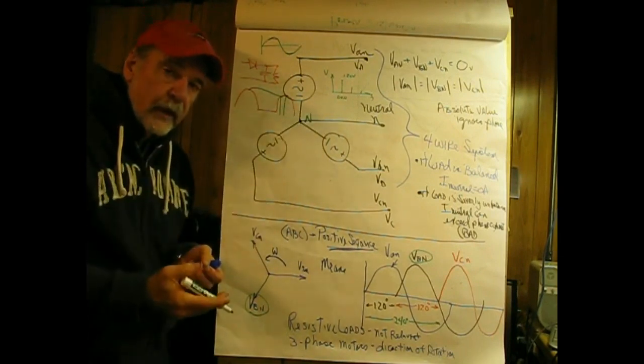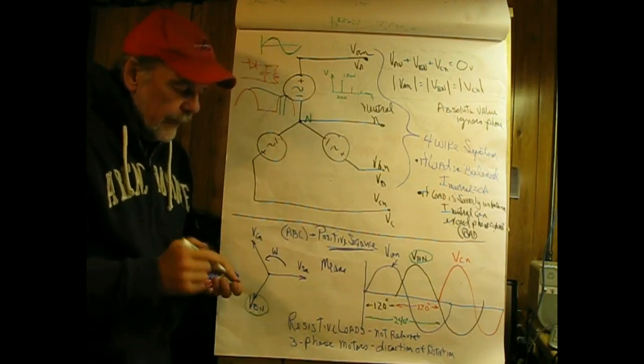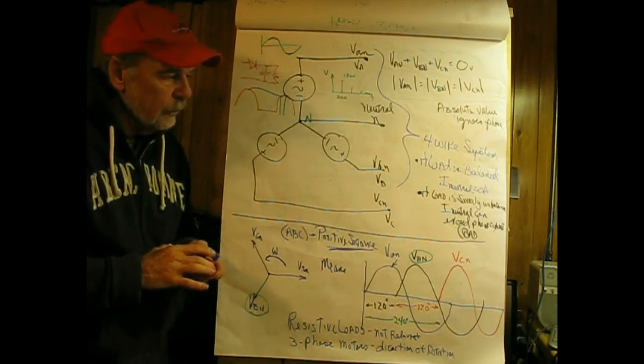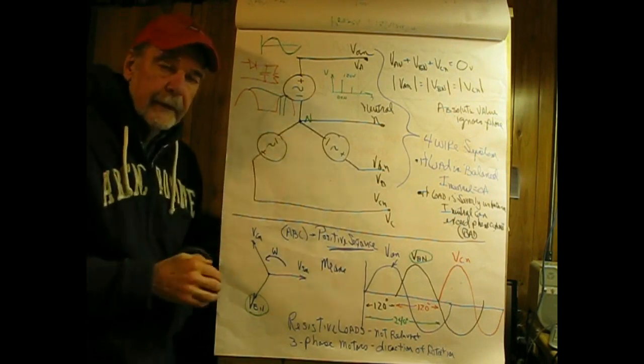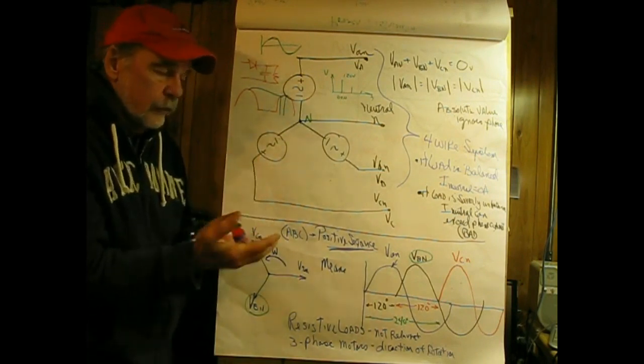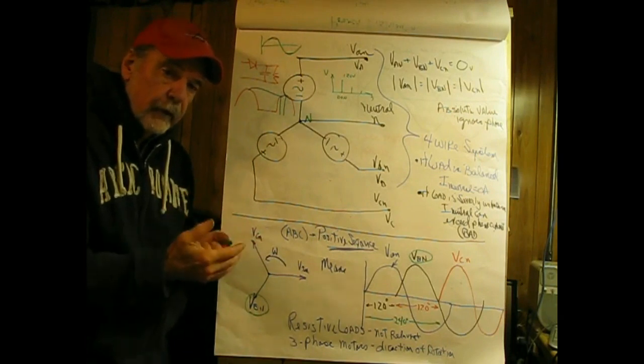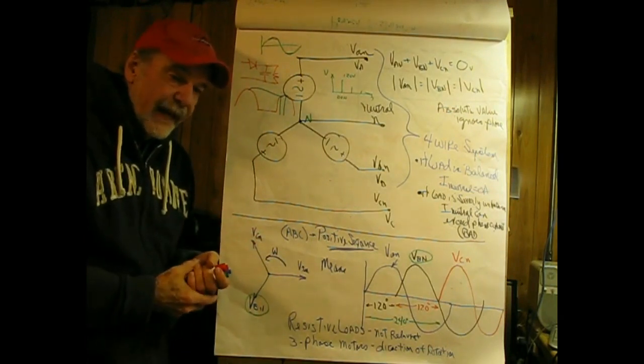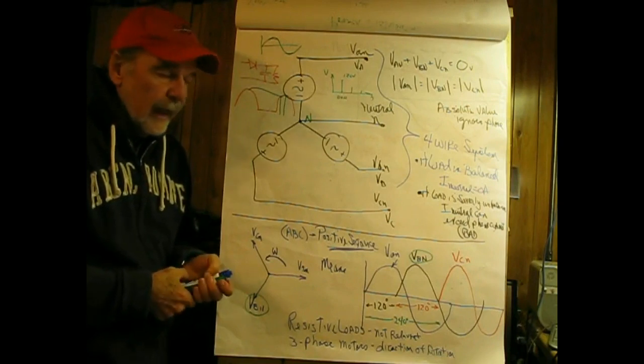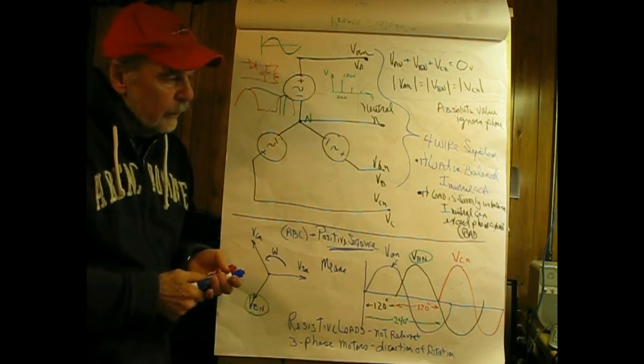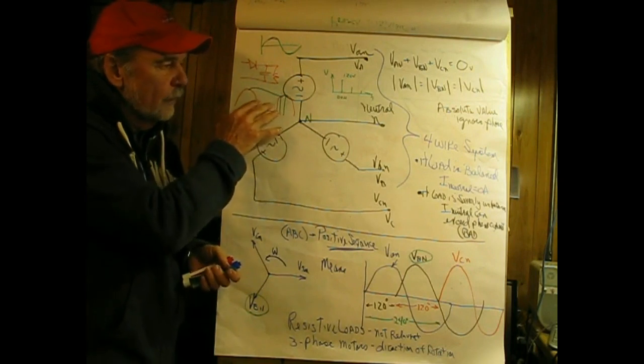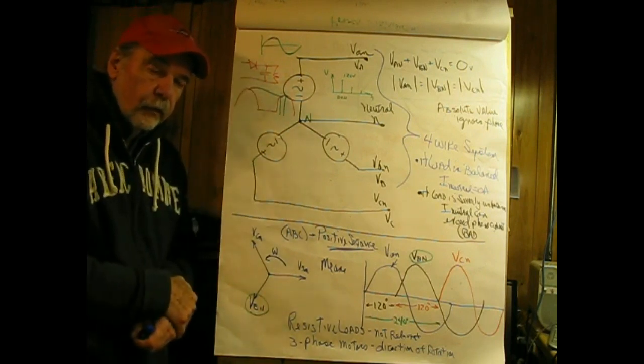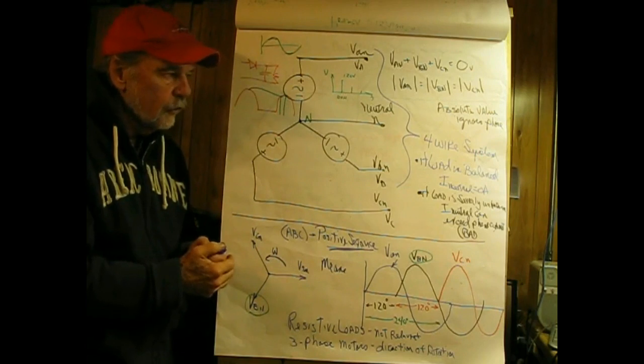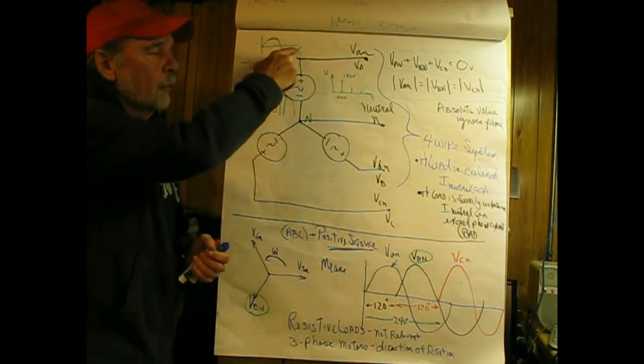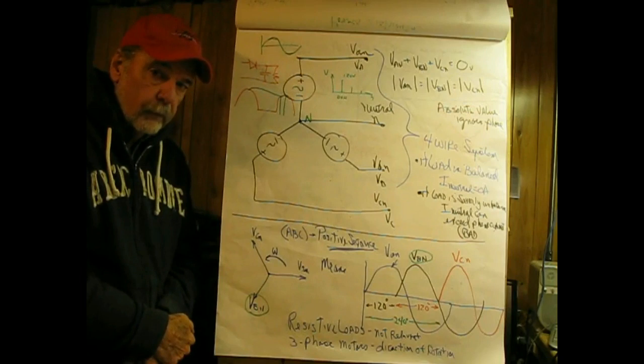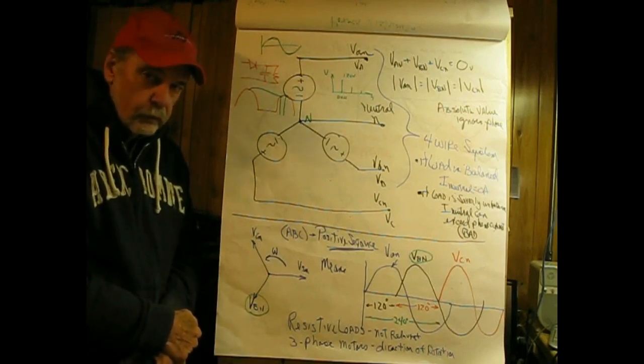They're producing currents which basically flow inside the plant, reducing the transformer's ability for the core to not saturate, causing I squared R losses and so forth. So modern power supplies, instead of using this technique, have inductors and capacitors in front of them such that current would flow through 360 degrees of the input waveform to reduce these triplens.